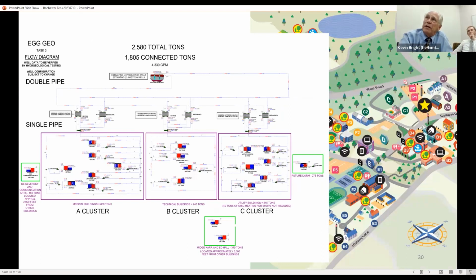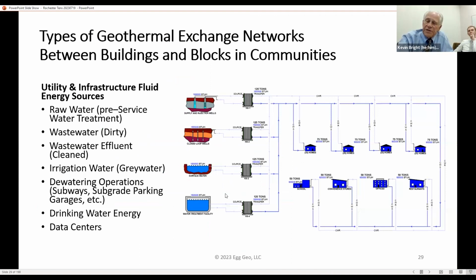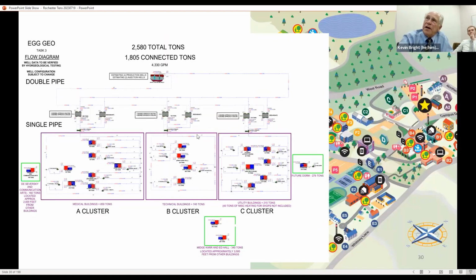Here's an example again of the one we showed earlier. One interesting thing about this technology is that it's a single pipe distribution system, not a two pipe. We run a loop around your neighborhood, then take off two pipes from that loop that run into your building and back out, and we either extract heat from that loop or reject heat to it.